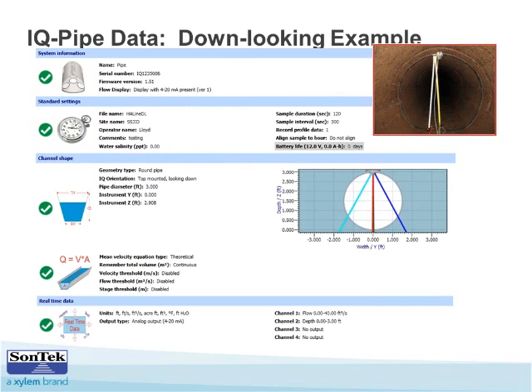This is a real world application showing how this instrument was set up in the field. We went down and entered some basic information. We set up our sample duration at 120 seconds, meaning the instrument will wake up, average for 120 seconds, and do that on an interval of 300 seconds.